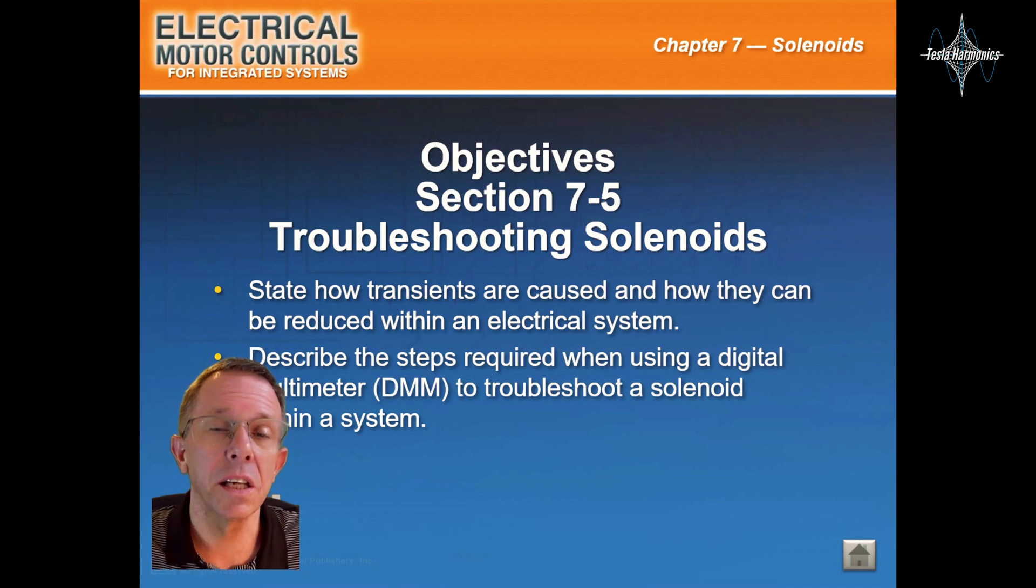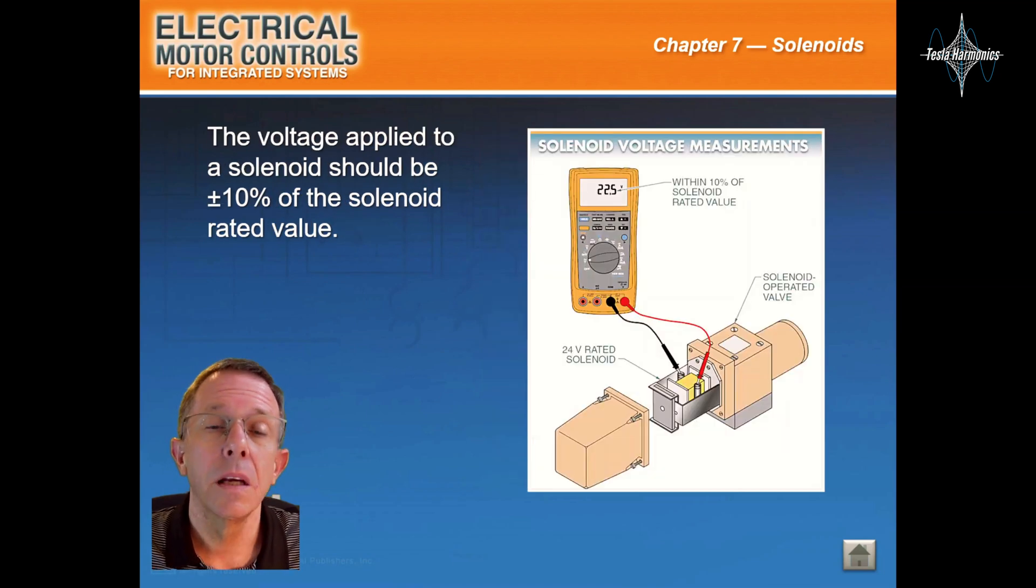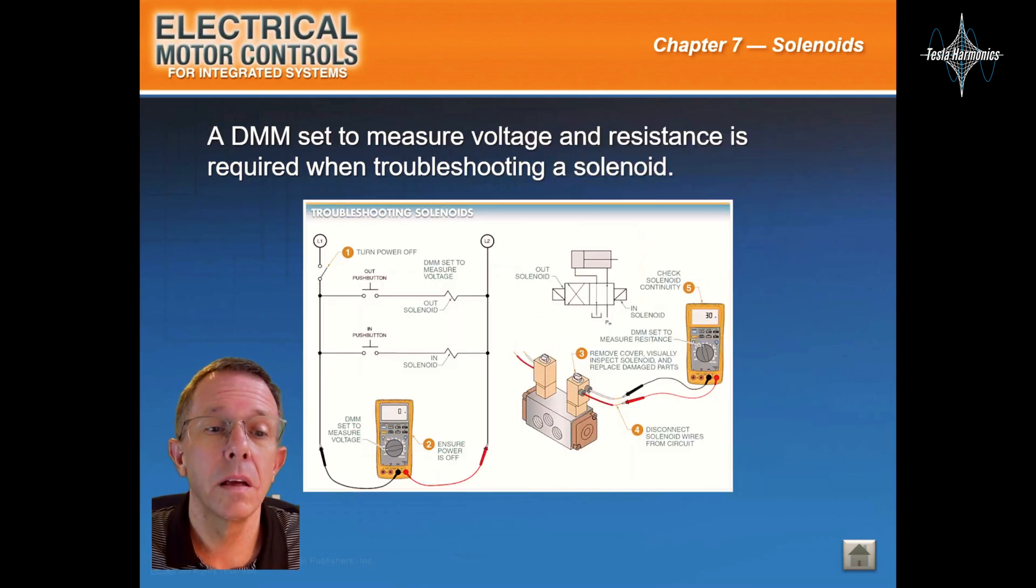This will be section 7-5 troubleshooting solenoids. Manufacturer charts are used to help determine the cause of solenoid failure. The voltage applied to a solenoid must be plus or minus 10% of the solenoid rated value. A DMM set to measure voltage and resistance is required when troubleshooting a solenoid.